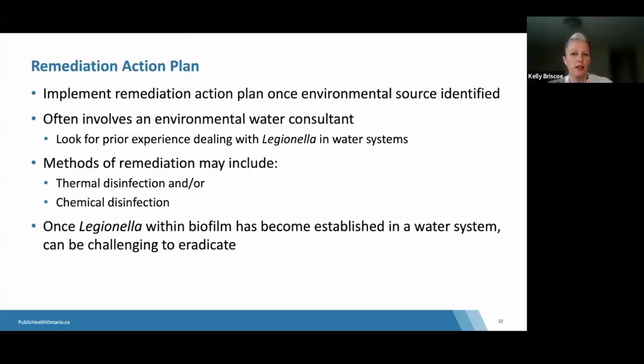Once the environmental source of Legionella has been identified, the owner or operator, and in some situations in collaboration with an external water consultant, may then develop and implement a remediation action plan. This remediation action plan should include disinfection procedures that are effective against Legionella and minimize the adverse impact on equipment and building occupants. A tailored approach accounting for water system characteristics, building uses, and any risk or benefit considerations of the treatment should guide the remediation plan. Many disinfectants are used to control Legionella and biofilm, and they can also be corrosive and may be detrimental to the equipment and materials within the system. This is again why it's important to consider working with a water system consultant to support the remediation plan.